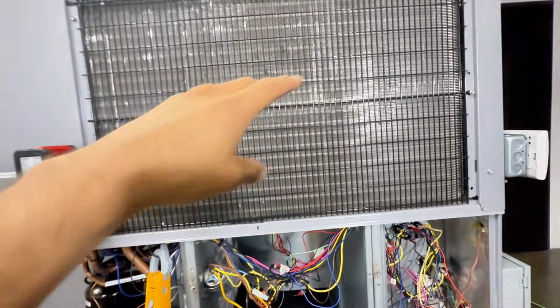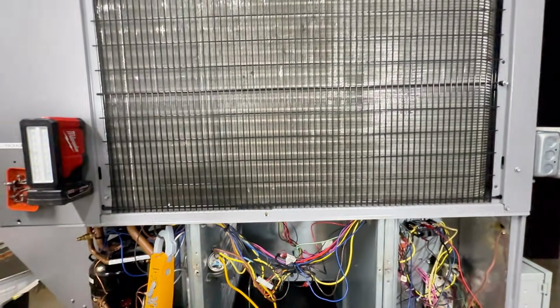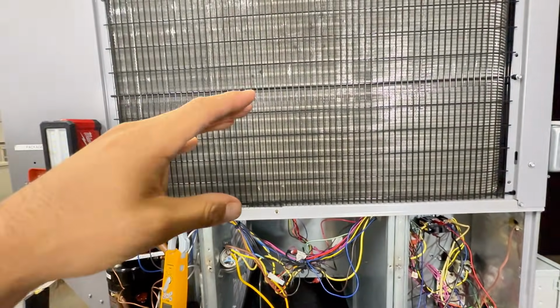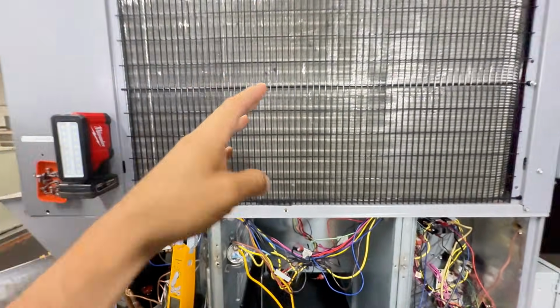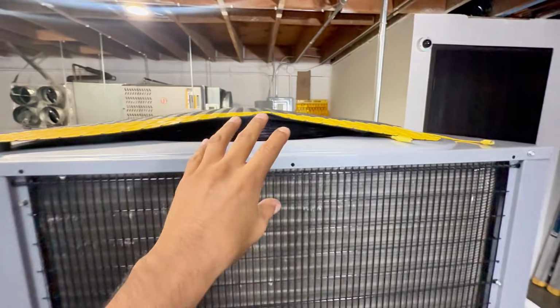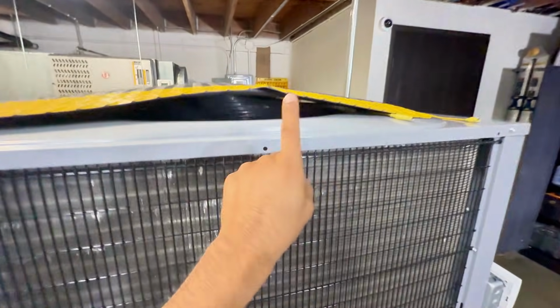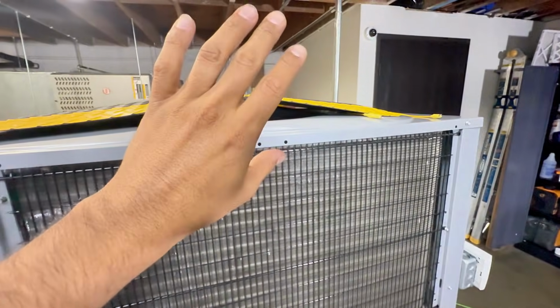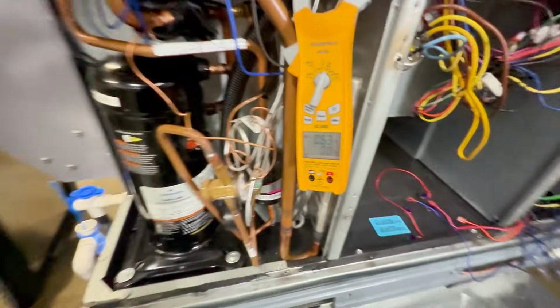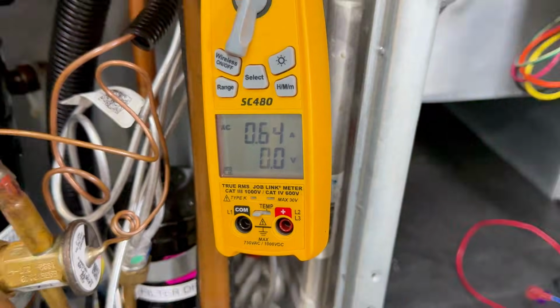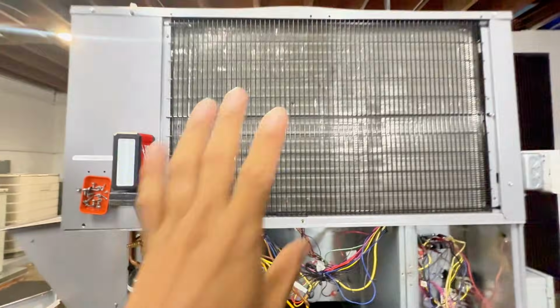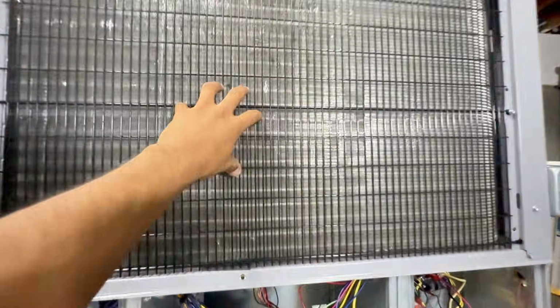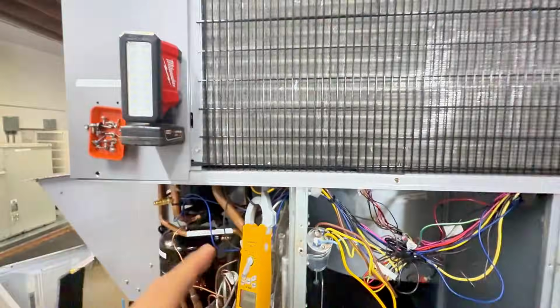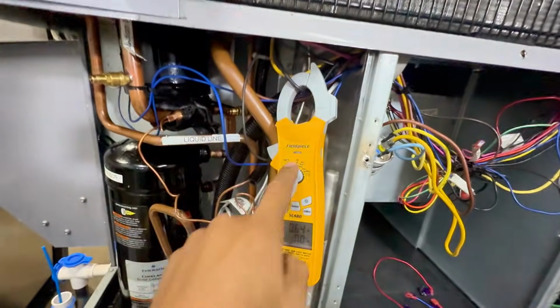And the way that this condenser fan works is under the concept of the way it is built. They call it a propeller fan, an axial fan. But right now it's trying to work harder. So it's actually spinning a little bit faster, doing more work to try to reject heat. But now if I take that out, it's going to return to 0.64 because it doesn't have that restriction. Now it can breathe, it can suck the air in through here and push it out through there. So as you can see, by checking amp draw, it can give you a symptom.